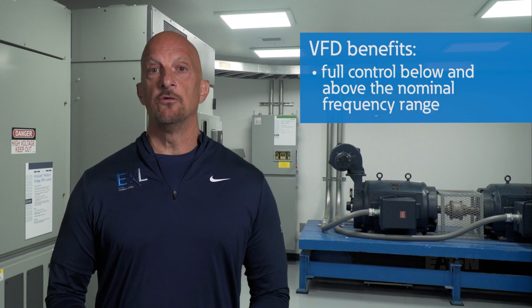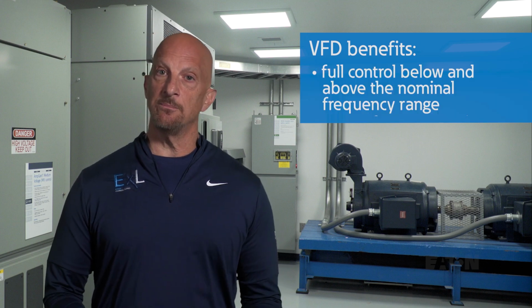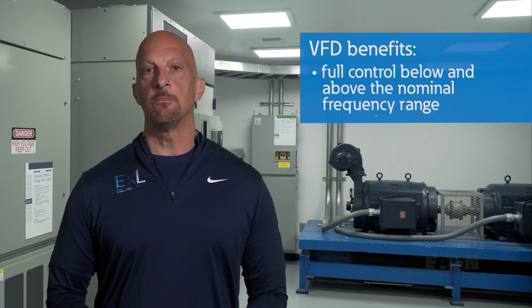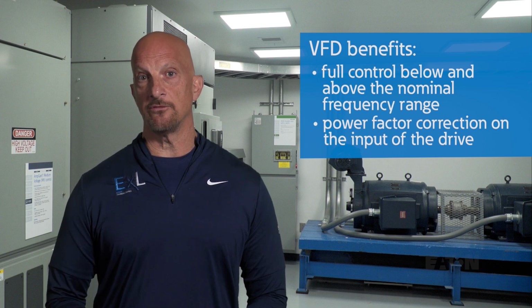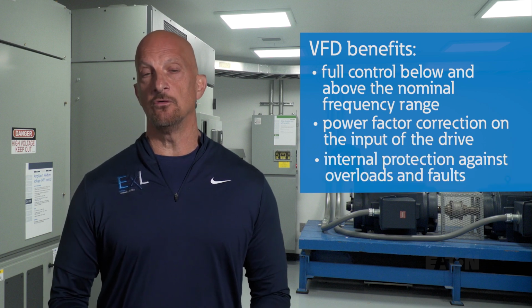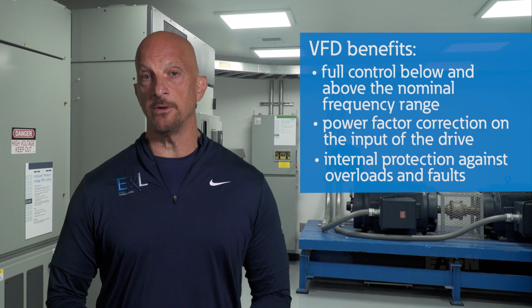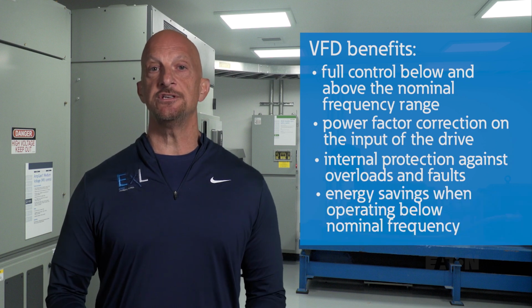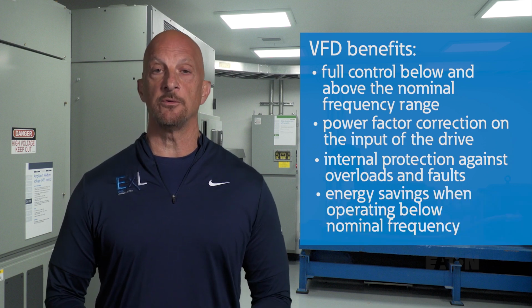Although the cost of the VFD is the highest of the 3, it offers other benefits, namely full control below and above nominal frequency range, power factor correction on the input of the drive, internal protection against overloads and faults with current limiting capability, and most importantly, energy savings when operating below the nominal frequency.